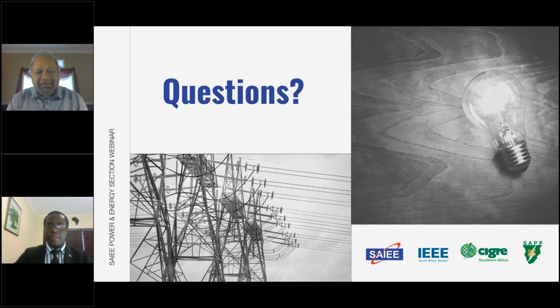That's an excellent question, because when you measure angle differences across any two points in the grid, it doesn't have to be across a line. You can take a measurement in Cape Town and one in Johannesburg, and that gives an indication of grid stress between those two points, across any electrical connection between them. Unlike a transmission line, which has a known limit like 50 or 100 megawatts, with angle differences you do not know what is a good angle difference versus a bad one.